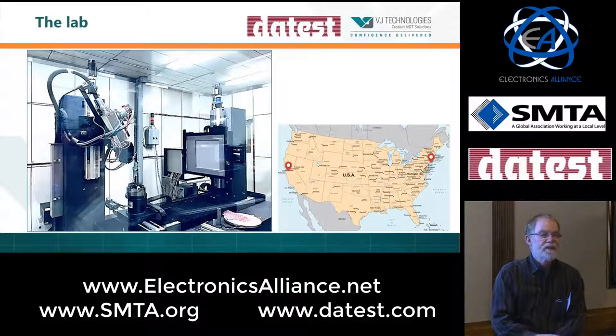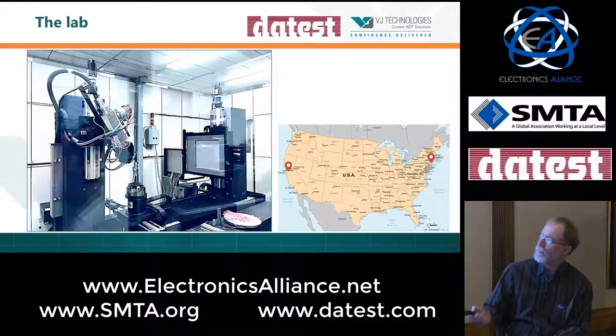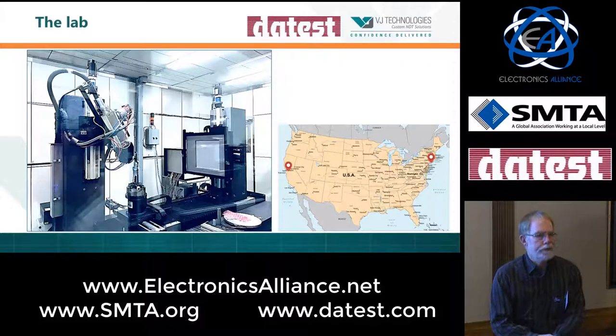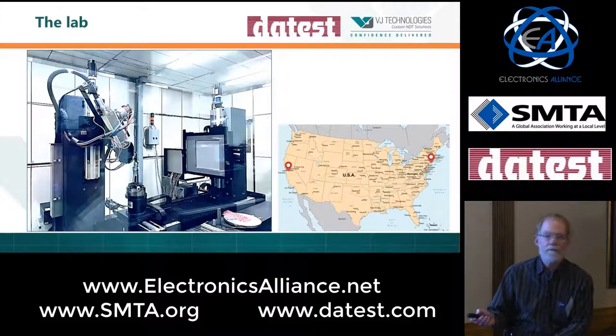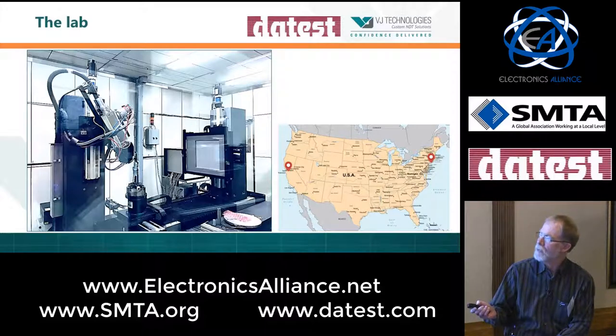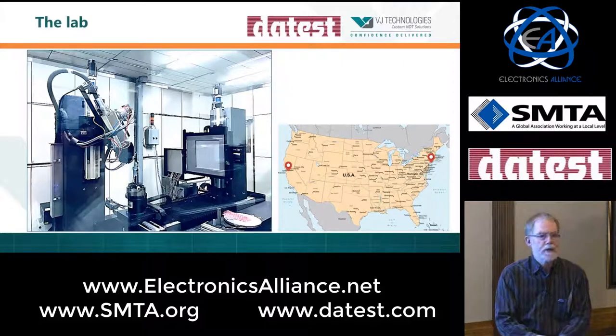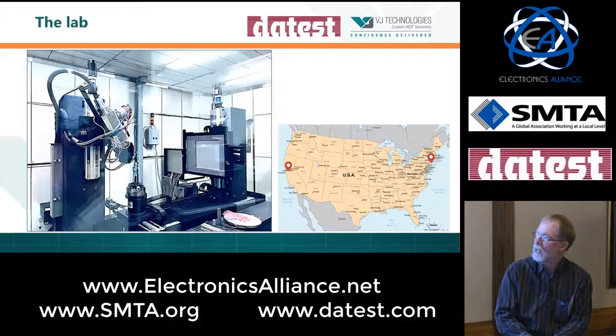This is what a CT scanning lab looks like. This happens to be ours in Fremont, California. This is what's called a vault system, and that simply means it's a system that sits inside a lead shielded room. Why? Because that's a 225 kV x-ray source, and it's sitting on 14,000 pounds of granite for stability. And it has a 16-inch by 16-inch 2048-pixel digital detector, Perkin-Elmer detector, and a very large chuck right in the middle, which holds the object of interest when it's being CT scanned.